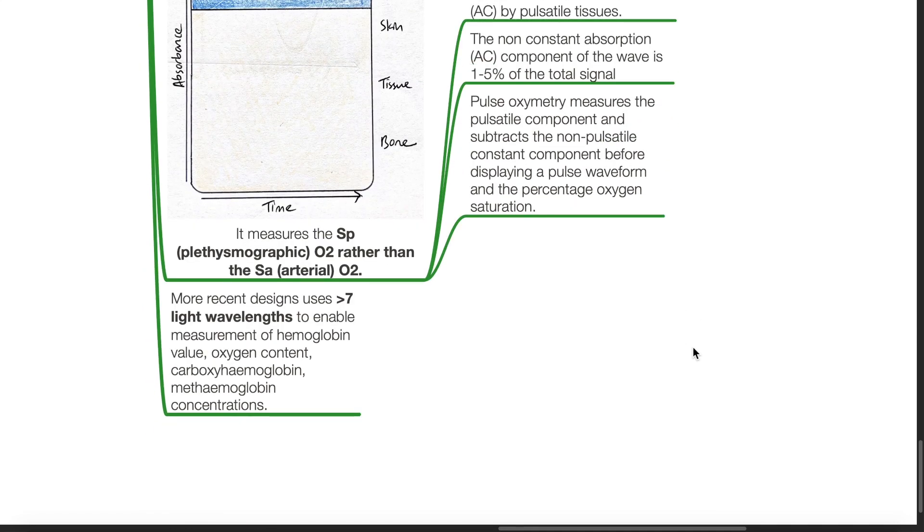More recent designs use more than 7 light wavelengths to enable the measurement of hemoglobin value, oxygen content, carboxyhemoglobin, and methemoglobin concentrations.